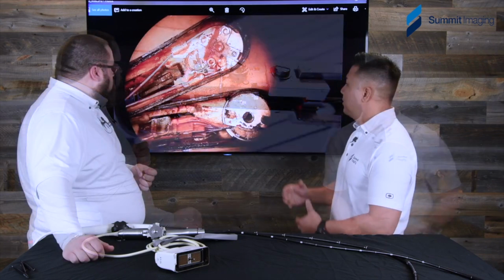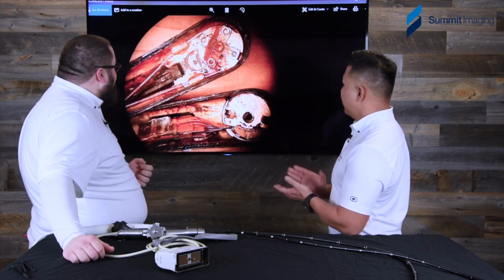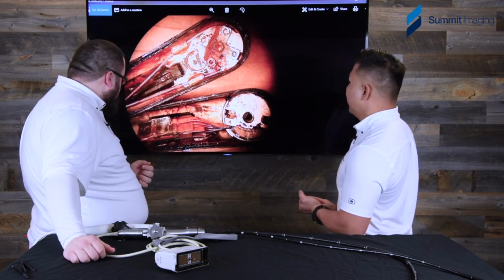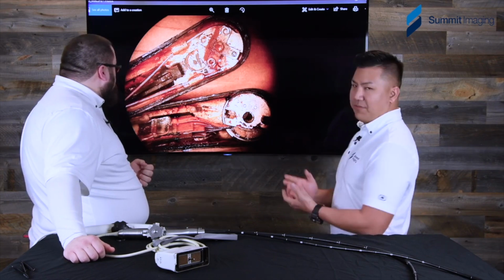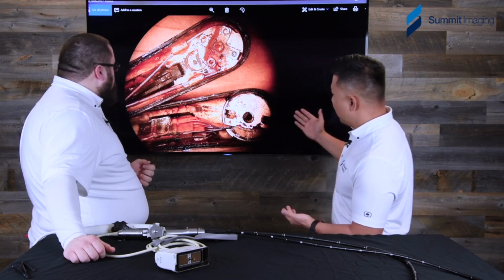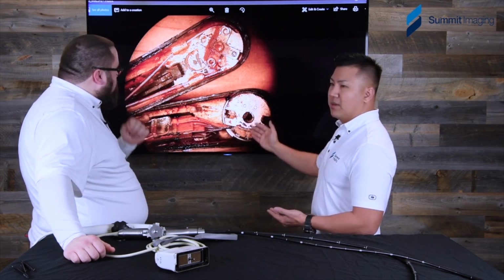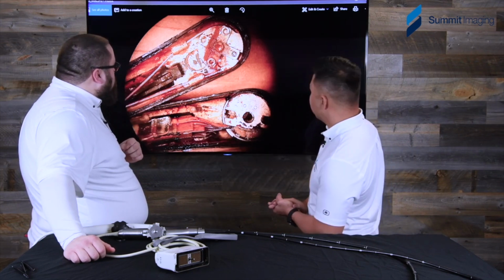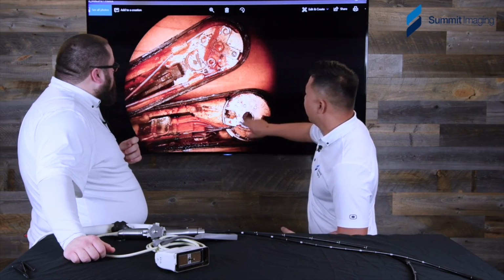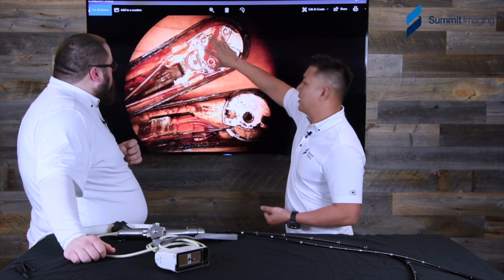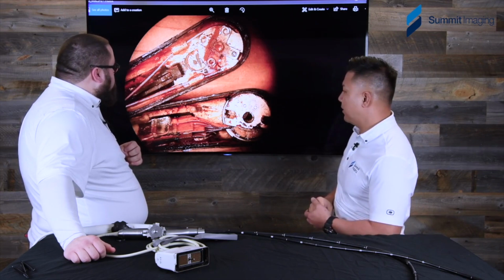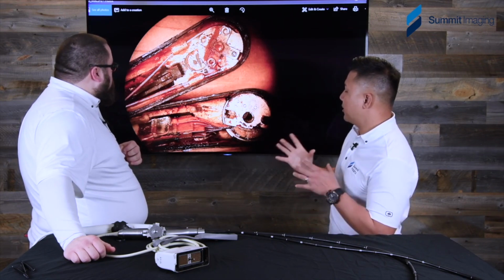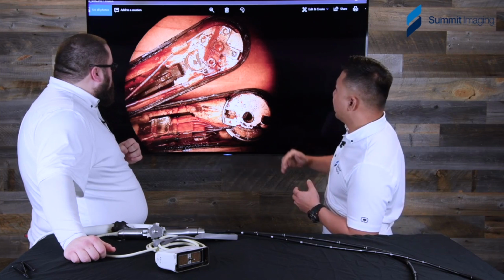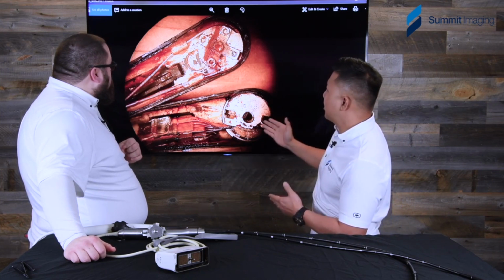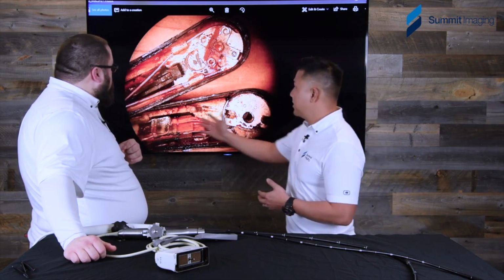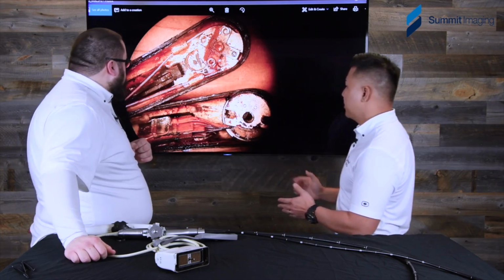All right. So the damage here is it's a pediatric TEE probe, and you can see that there was a lot of fluid intrusion throughout the entire internals of this transducer on the tip. The crystal is actually face down here, and that sits on top of this disc that rotates the crystal for the physician to get the image that they need at the right angle. But this is not supposed to be brownish orange. This is actually rust. Everything is rusted out.